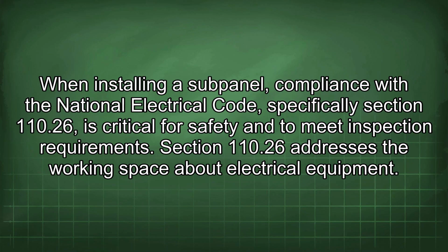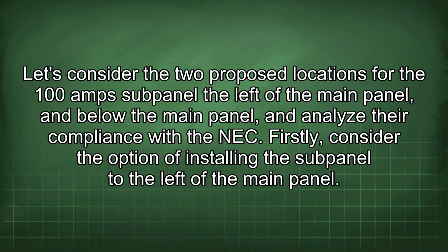When installing a subpanel, compliance with the National Electrical Code, specifically Section 110.26, is critical for safety and to meet inspection requirements. Section 110.26 addresses the working space about electrical equipment. Let's consider the two proposed locations for the 100 amp subpanel, left of the main panel and below the main panel, and analyze their compliance with the NEC.